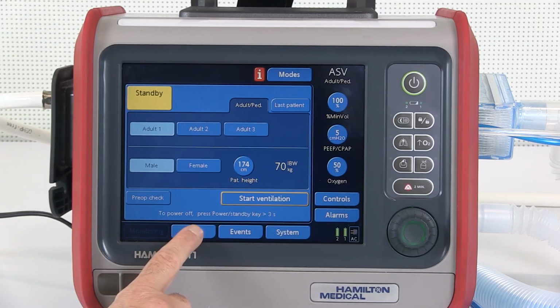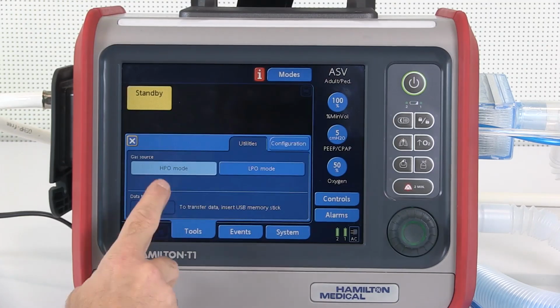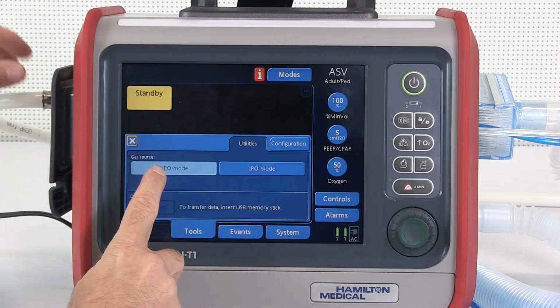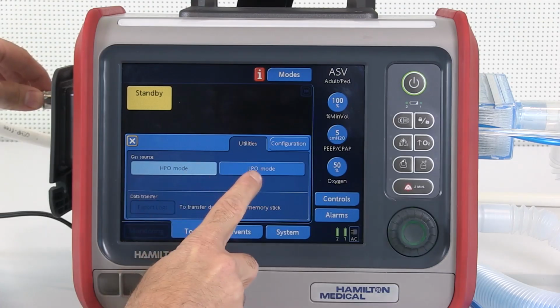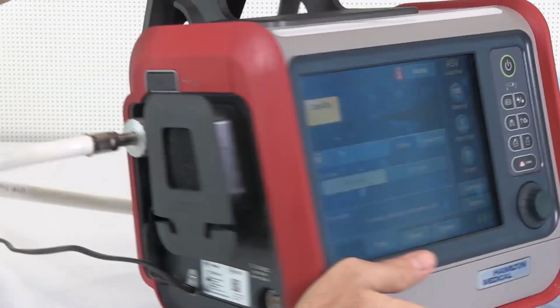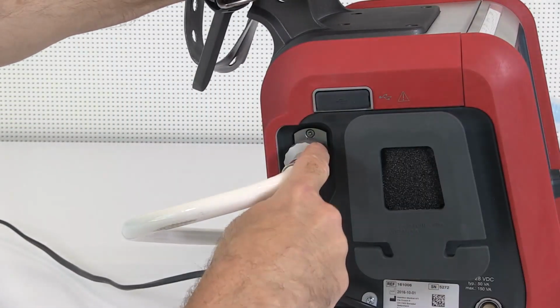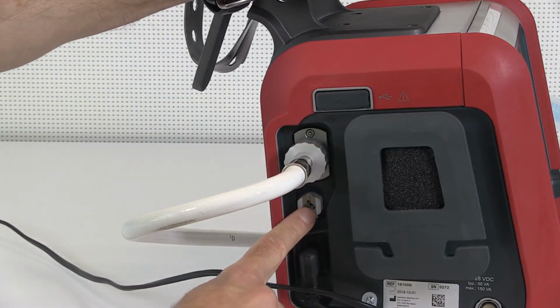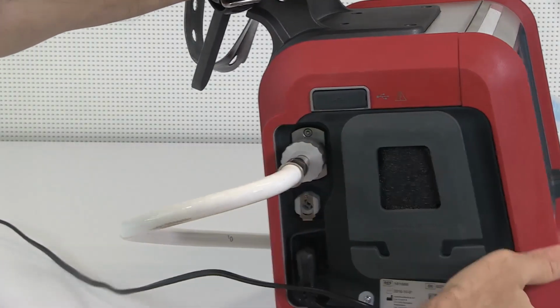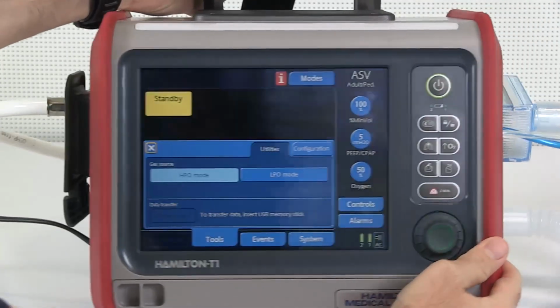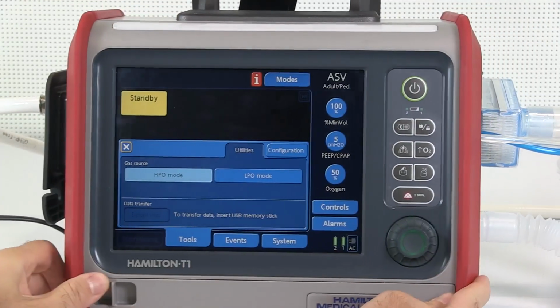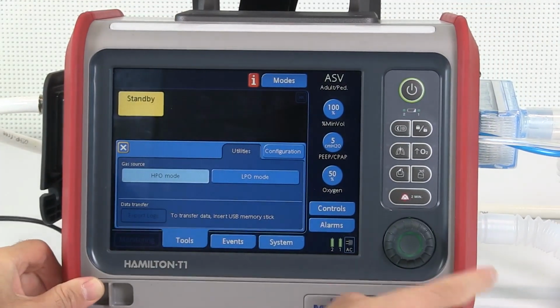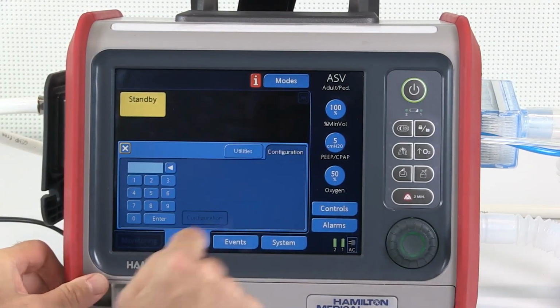Touch Tools. Here, you can set the gas source to either high-pressure oxygen or low-pressure oxygen. A high-pressure oxygen supply is connected to this ventilator unit. Make sure that no LPO connector is attached when the ventilator is configured to HPO, as this will cause a technical failure alarm. Touch Configuration.